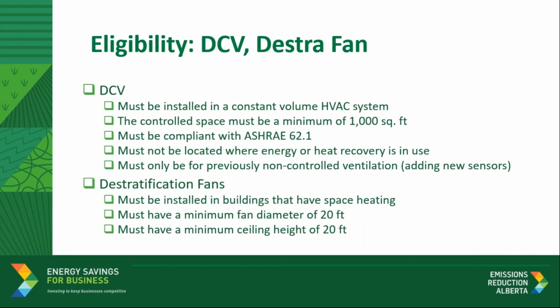Continuing with the eligibility for DCVs, they must be installed in a constant volume HVAC system. The control space must be a minimum of 1,000 square feet. The system must be compliant with ASHRAE 62.1. They must not be located where the energy or heat recovery is in use, and must only be for previously non-controlled ventilation. So you're adding new sensors. Lastly, for the destratification fans, they must be installed in buildings that have space heating. The minimum fan diameter is 20 feet, and the minimum ceiling height is also 20 feet.